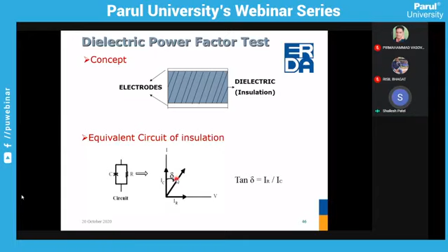A standard capacitor has no leakage paths. It is SF6 gas filled, and its capacitance is normally very low. For 800 kV, its capacitance is 20 picofarad. For another level, its capacitance is nearly 100 picofarad. For 600 kV, 500 kV, the capacitance will be nearly 50 picofarad. As we go on increasing the voltage level, the capacitance value is reduced, correct?